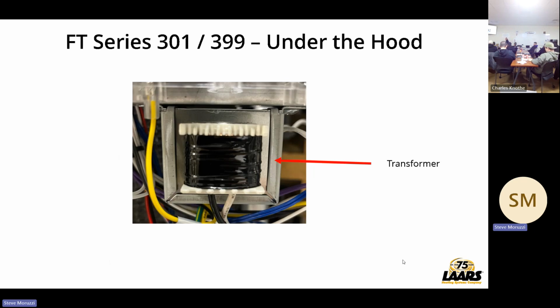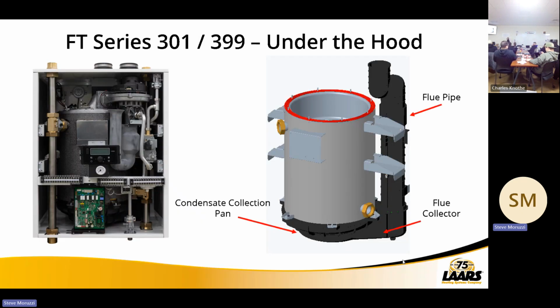And a very small transformer. Again, we're not trying to power your Ecobee, your Nest thermostats, all of that, or control zone panels or zones. This transformer is for the boiler, and it is fuse protected.